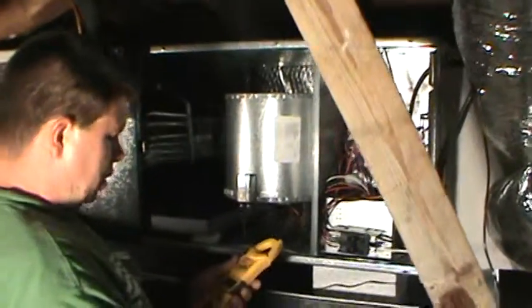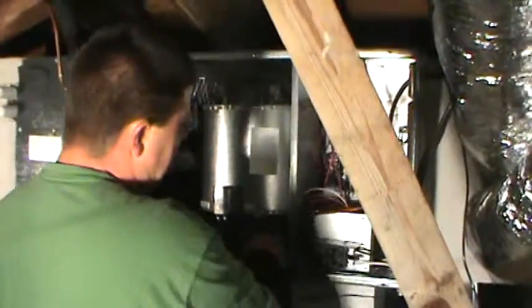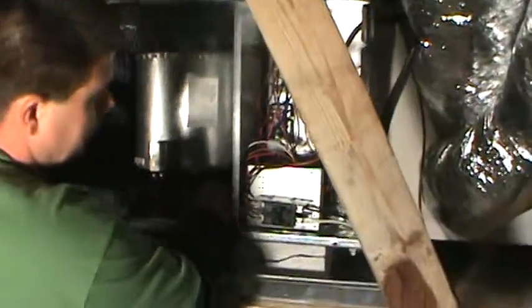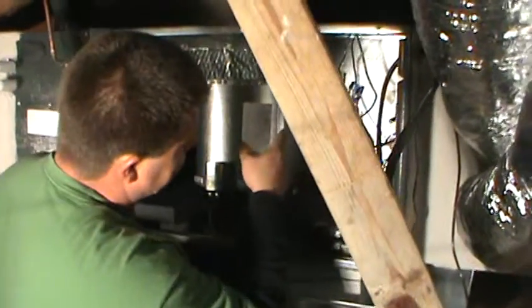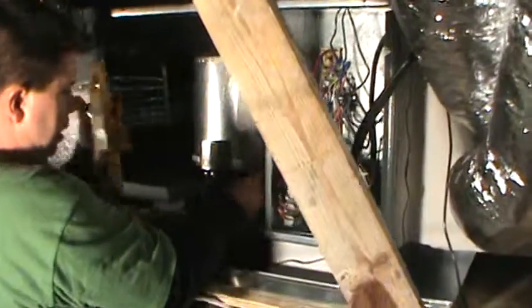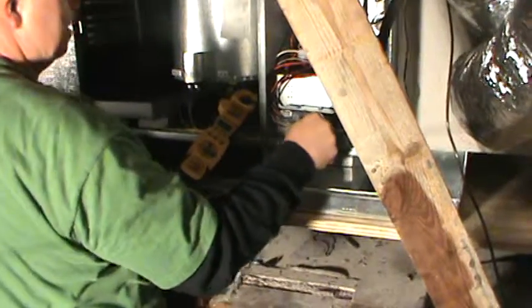So set your multimeter to amps. You want to find your common wire for the fan motor, which usually is going to be the wire on your fan relay. On this one here it's blue, so I'll find my blue wire, make sure that's the only wire in your amp probe, get that on. I'm going to turn the power on.